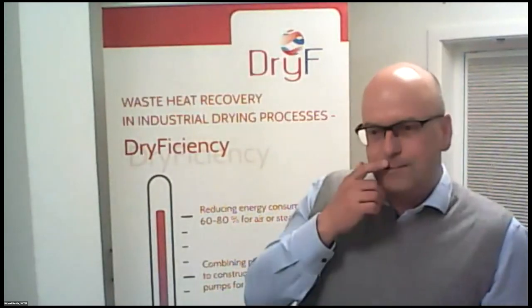I think we are aiming for continuous operation, right? We start up once, because the startup procedures in high temperature heat pumps are in general a little bit tricky maybe. So we want to start it up once and then have it in operation for as many hours as possible. Of course, if the heat pump doesn't work, it doesn't reduce emissions. That is just very simple mathematics, but ideally we would be aiming for 6,000, 8,000 operational hours during a year. And then you don't shut it down on a daily basis.